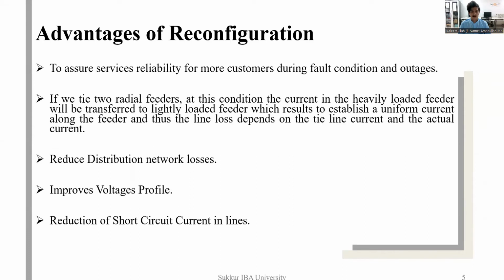There are significant advantages of reconfiguration. Some of them are to assure service reliability for more customers during fault conditions and outages. If we tie two radial feeders, the current in the heavily loaded feeders will be transferred towards the lightly loaded feeders, which establishes a uniform current along the feeders. Thus, the losses depend on the tie line current and the actual current. By reconfiguration, we can reduce our distribution network losses. Also, it improves our voltage profile. Moreover, it reduces the short circuit current in the lines.